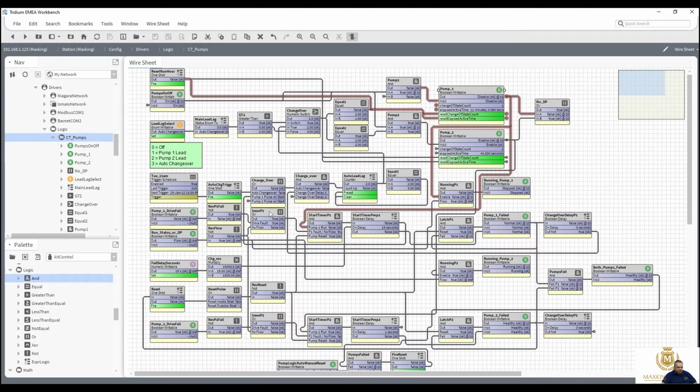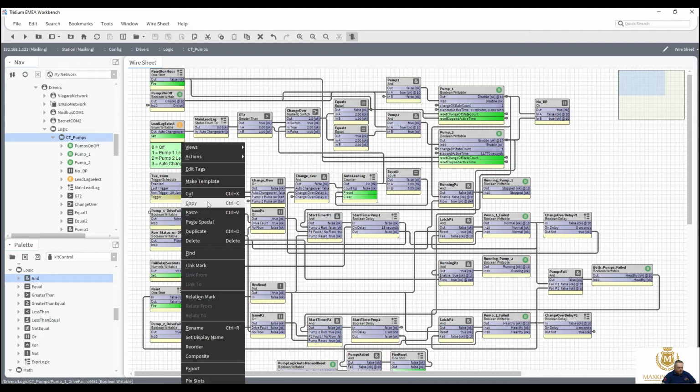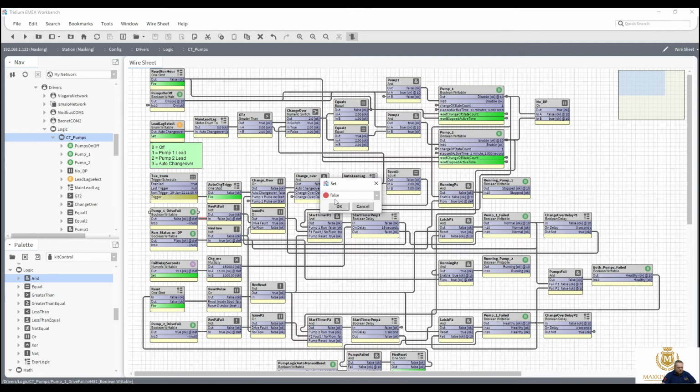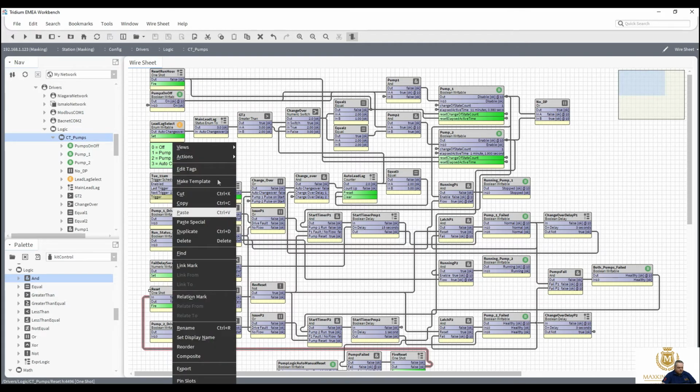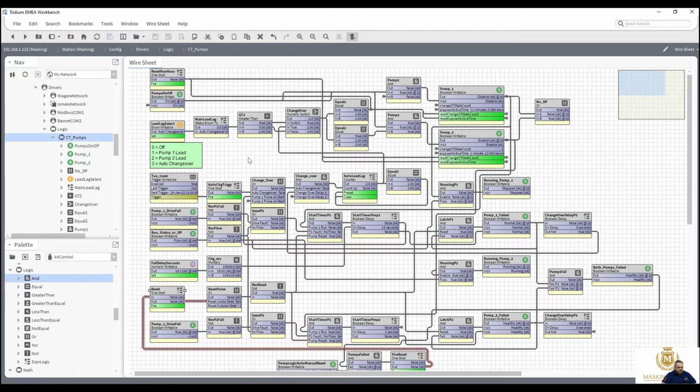So we're running on pump 2 because that's now failed. Let's put that back to normal. Set to true. Reset everything. Fire reset. So it's using this pump anyway because it's run the minimum. Not that I'm taking that into consideration, so it shouldn't be. So auto changeover is working on pump 2 first.